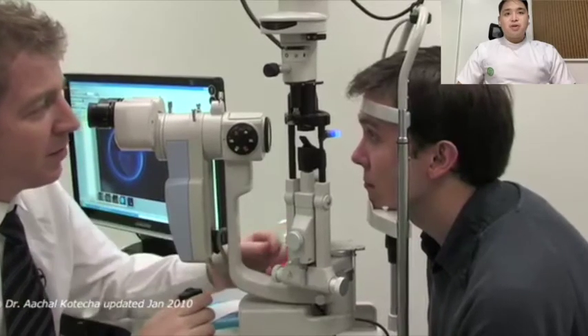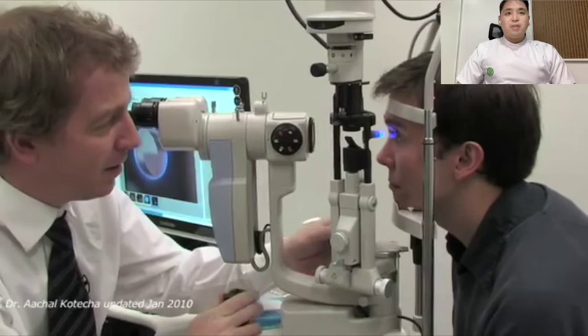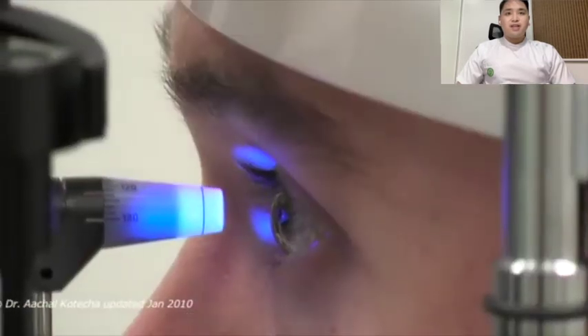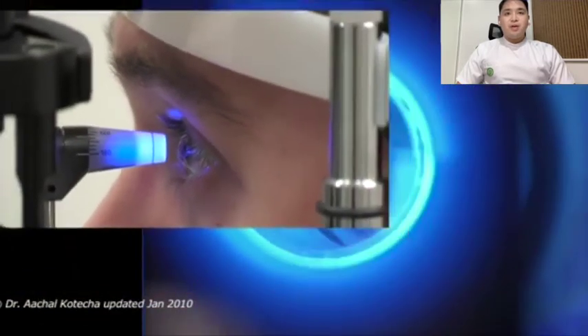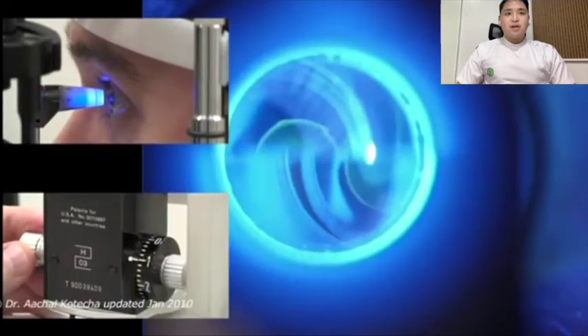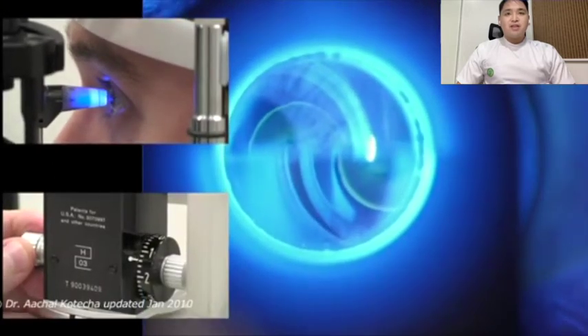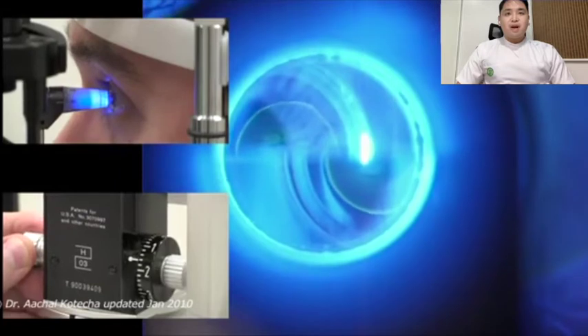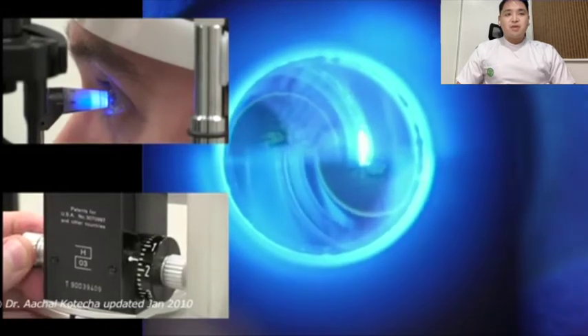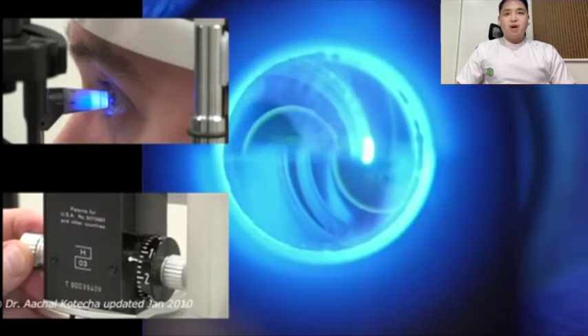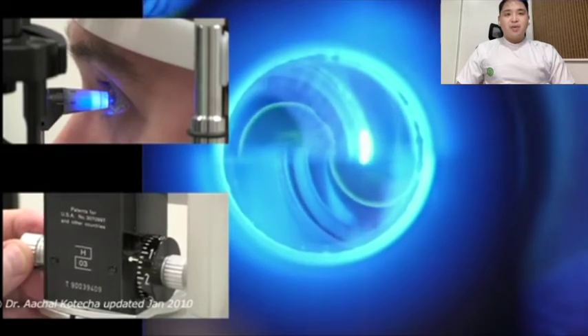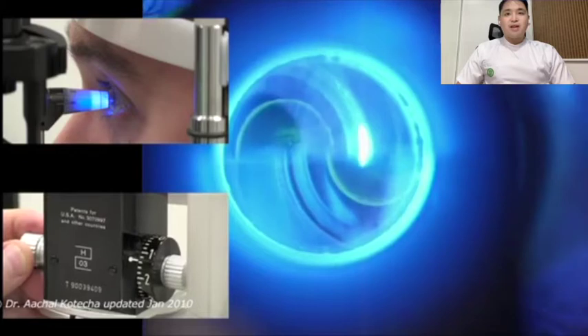Using the slit lamp control handle, gently move the biprism forward until it just touches the cornea. Looking through the slit lamp oculars, confirm that the biprism has just touched the cornea. The spot of fluorescence will break into two semicircles, one above and one below a horizontal line. Raise and lower the slit lamp biomicroscope with a control handle until the semicircles are equal in size.